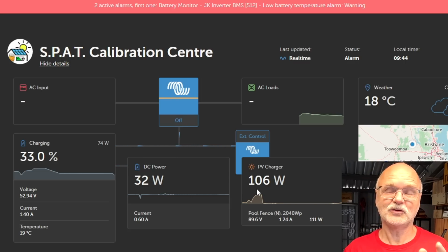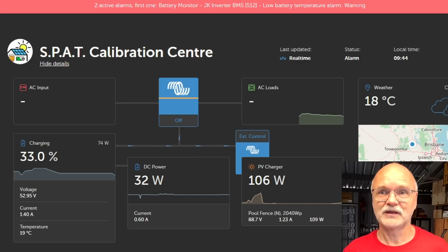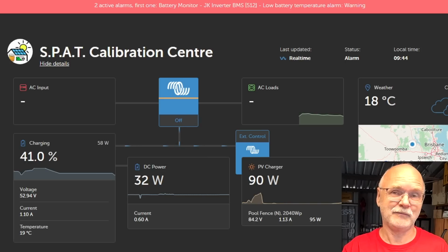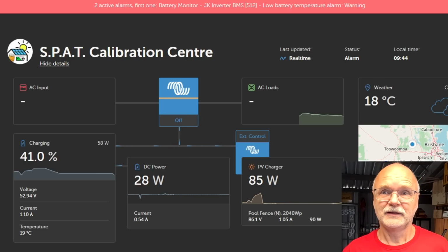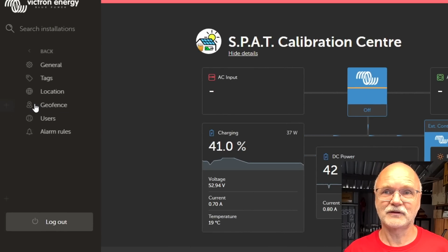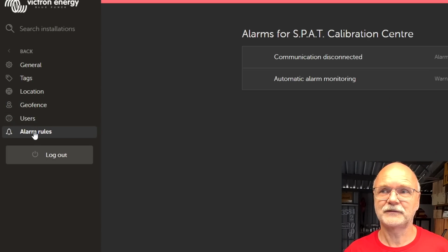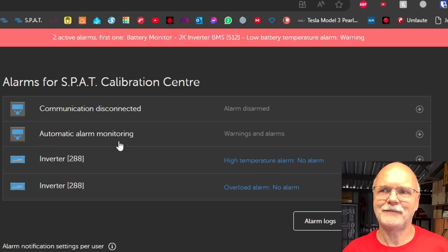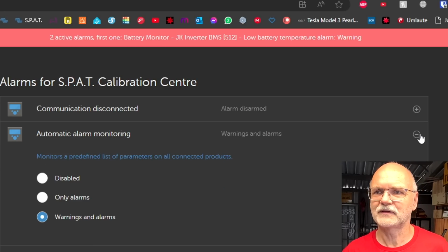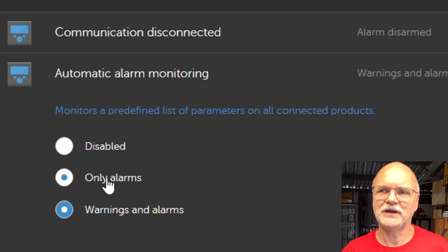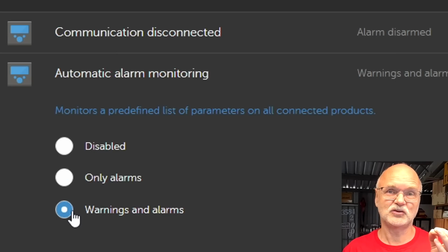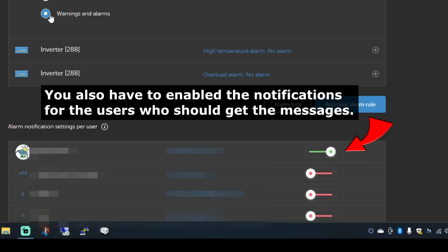But here in the VRM, you need to change a setting if you haven't already done this to get the push notifications onto your mobile phone. So obviously you need to have the VRM app installed on your mobile phone. Then you go into settings, you go into alarm rules. And here under automatic alarm monitoring, you click on this little plus and you change it from only alarms to warnings and alarms. I think as per default it sits on alarms only, but you have to change it to warnings and alarms, otherwise you don't get any notifications on your mobile phone.